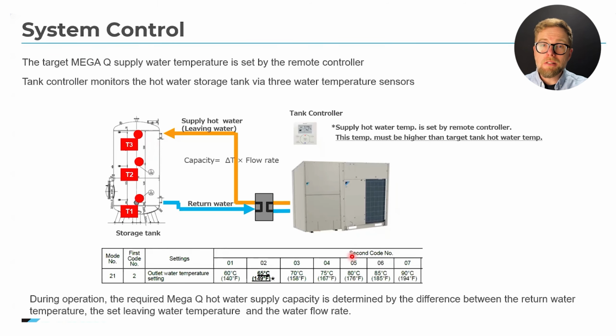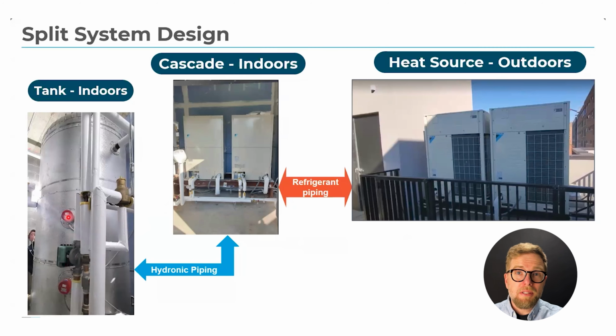As I mentioned, this includes 3 water temperature sensors that you place on the top, middle, and bottom of your water storage tank. By reading these different temperature layers, the control logic knows exactly when to ramp up or down those compressors and how fast or slow to run those integrated water pumps. You're not guessing about water temperature, it's monitored in real time, which leads to more consistent hot water delivery and better energy efficiency. The split design is another game changer.